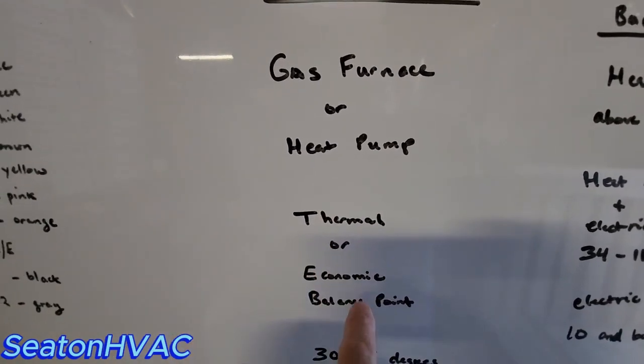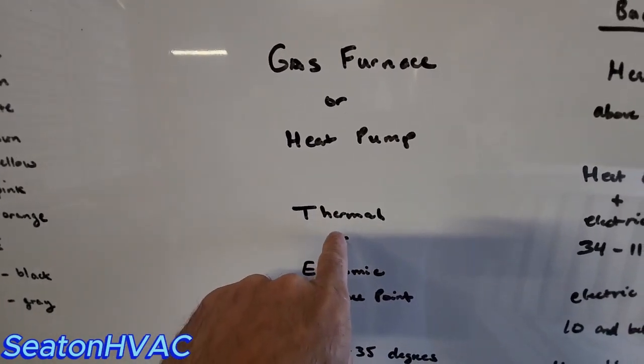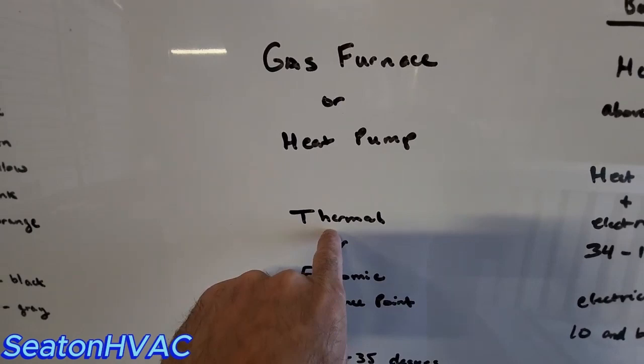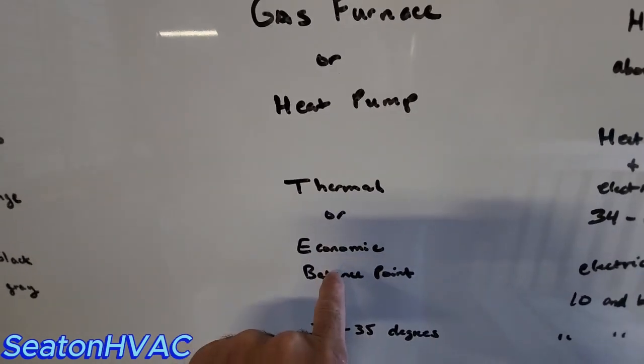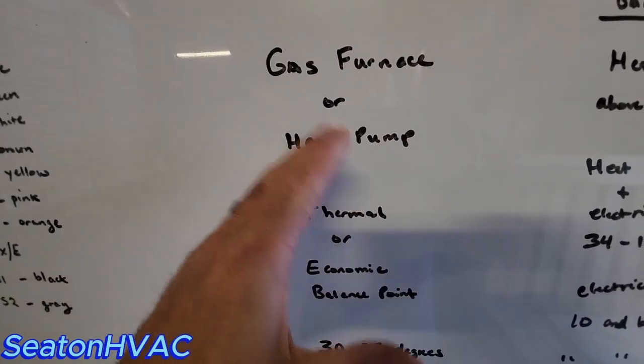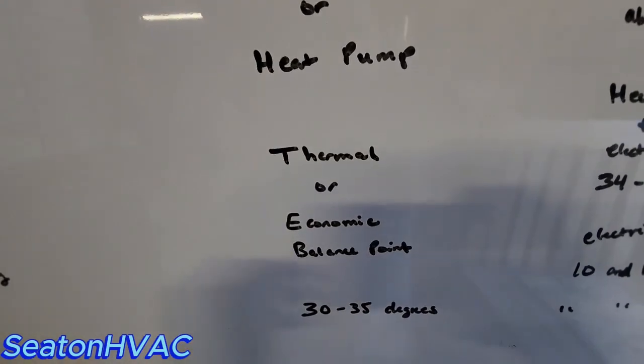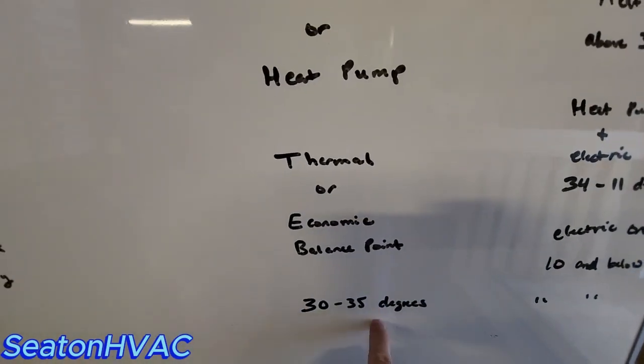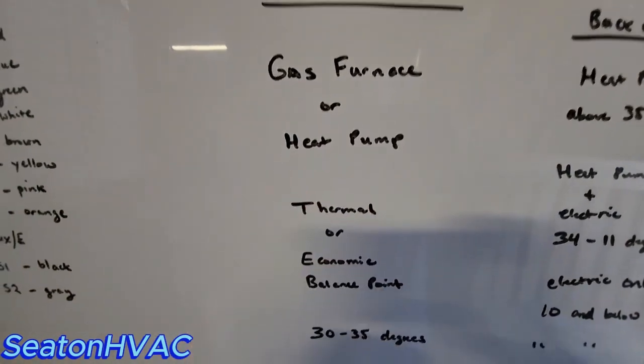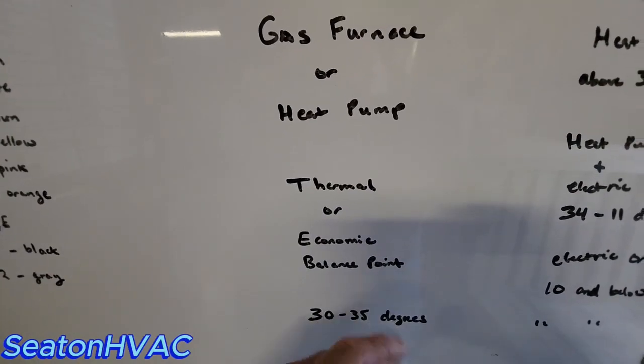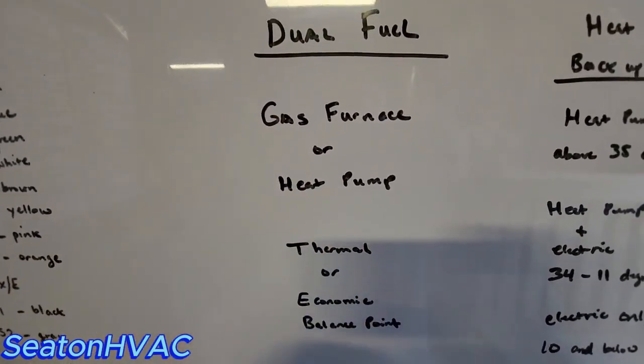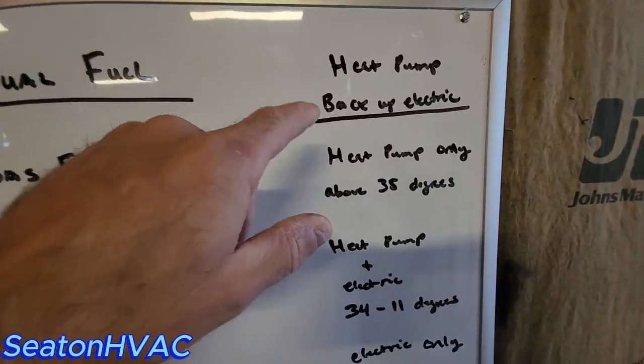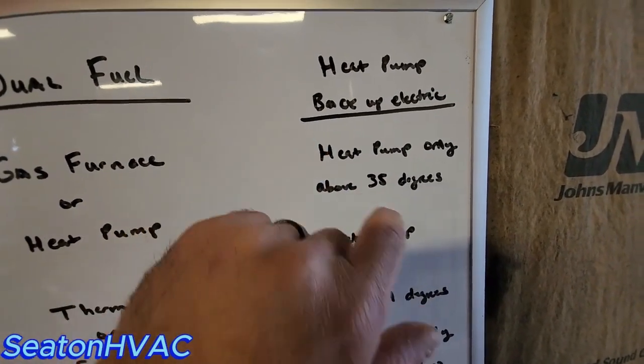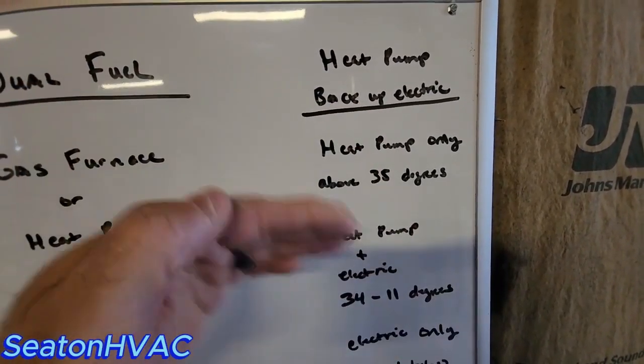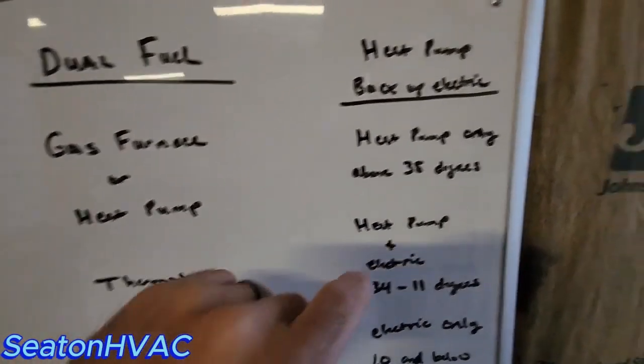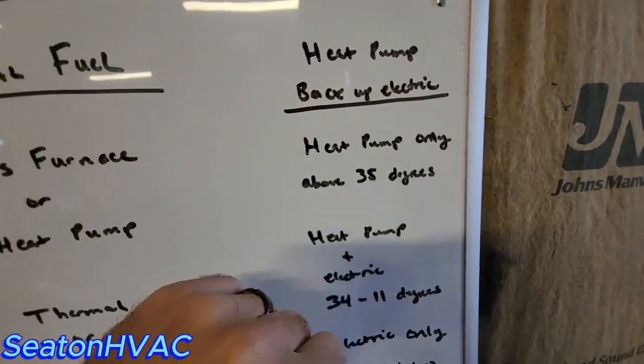But I'm just giving you guys terms that you can look up if you're not familiar with them. So look up a thermal balance point. Just do a Google search versus economic balance point. It'll explain all that to you. I'm not going to get into it on my whiteboard here. Typically, it's about 30 to 35 degrees is what most systems are set at, but you can set them a lot lower or even higher depending on how the numbers come out, okay? Heat pump with backup electric heat. It's heat pump only above 35 degrees or whatever that economic or thermal balance point is between heat pump and electric, okay?